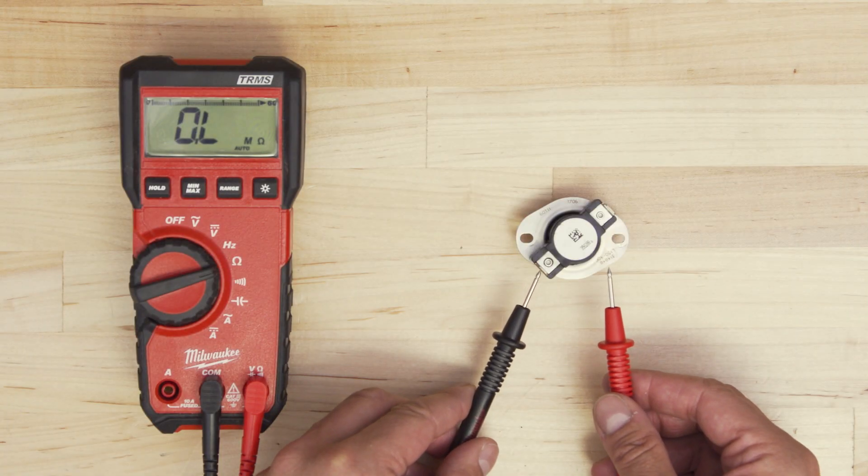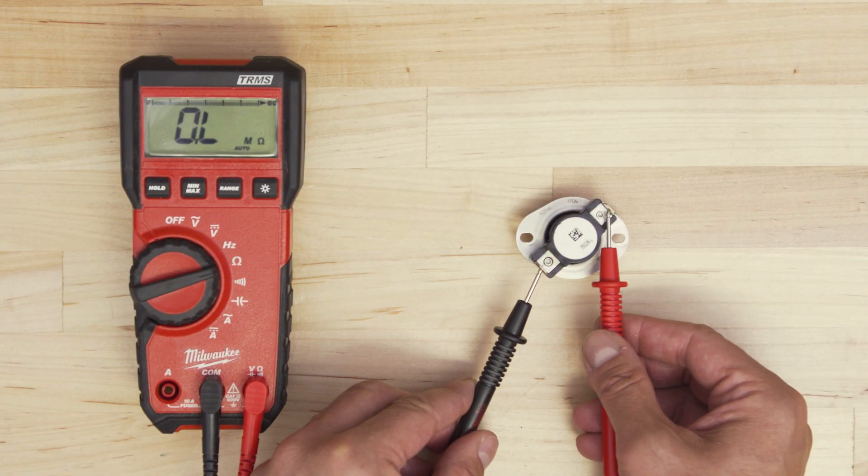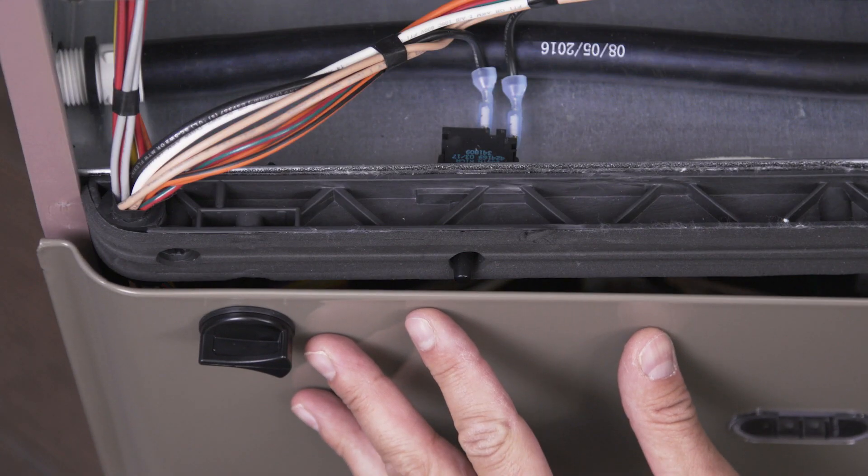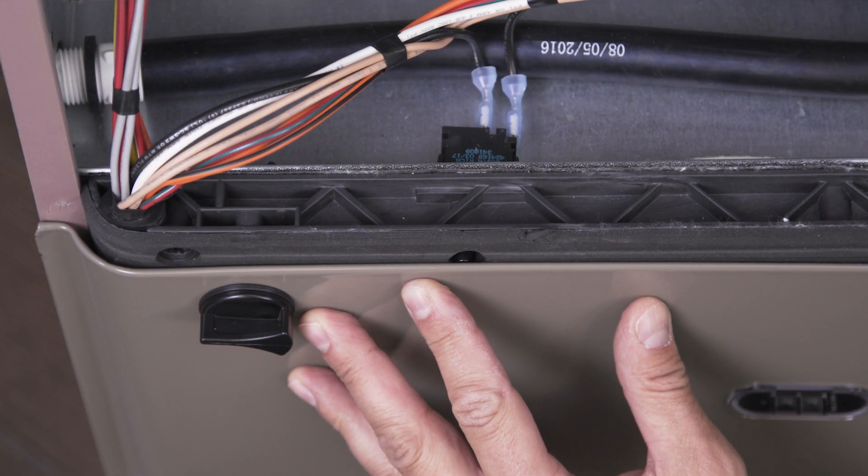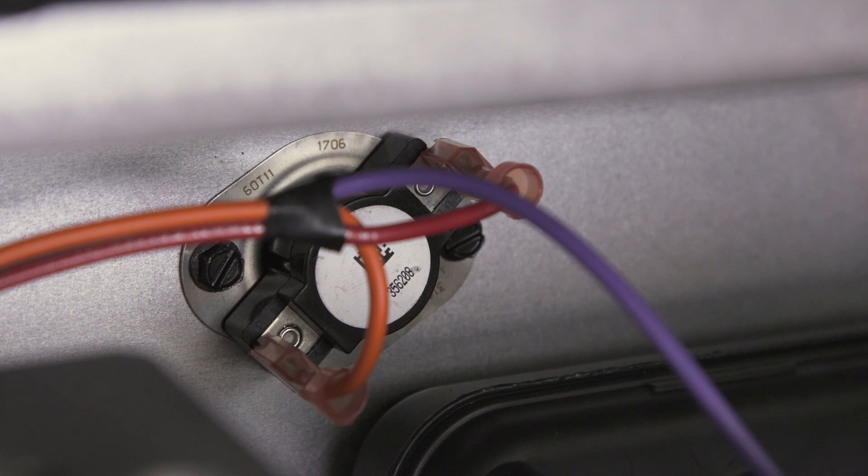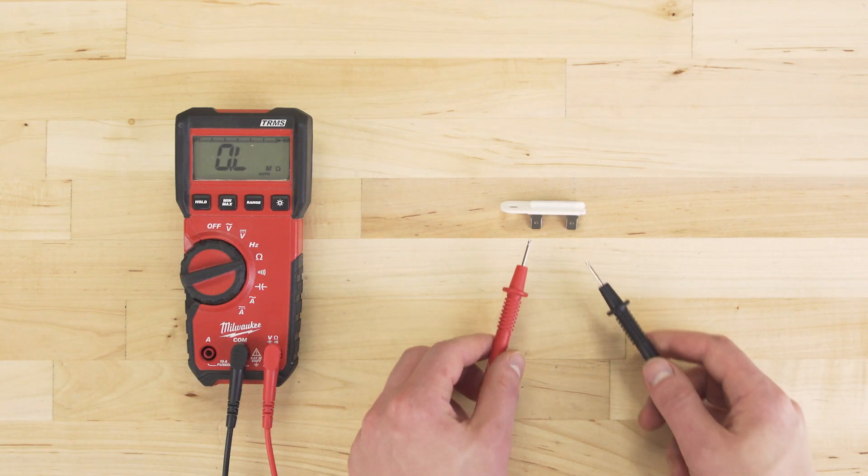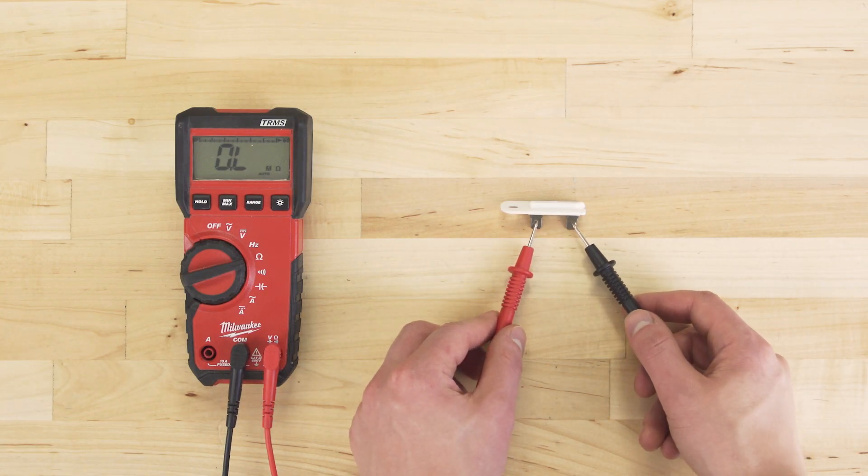If there is continuity, you'll get a reading above zero ohms. But the resistance will vary between load or non-load components. Non-load components, such as switches, thermostats, or fuses, provide an unrestricted path for the electricity to pass through. These will typically have a resistance reading between 0 and 1 ohms.